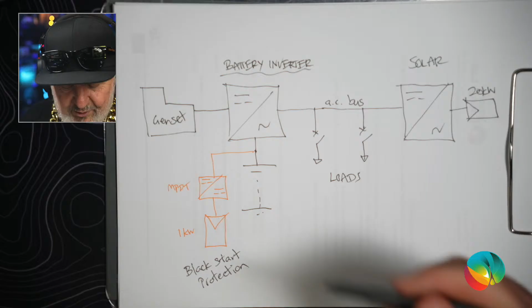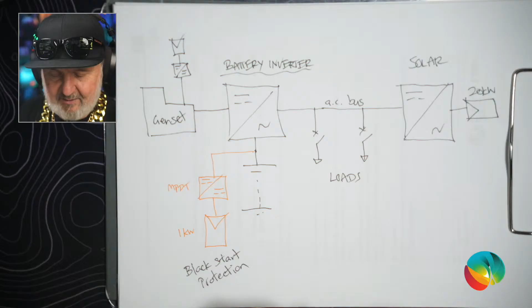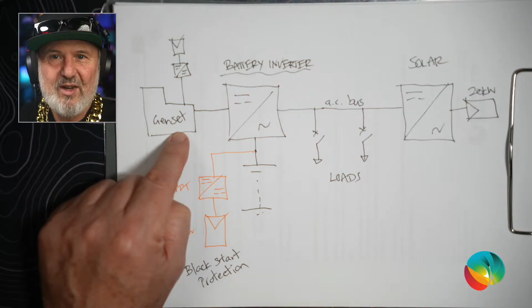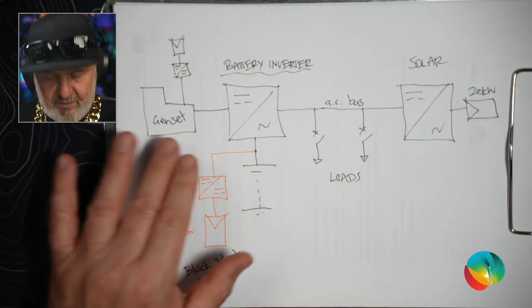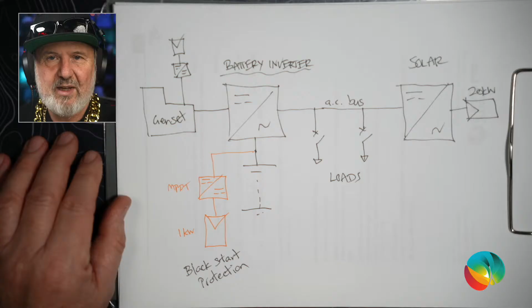Can I also suggest that if you're going to have black start protection, you should also have some way of charging the battery on your generating set. So put in even just a little one panel to keep the generator set battery charged up, because if you've designed this system to have a high solar fraction, that means you hardly ever use the generator. So here at the Smart Energy Lab, we don't run the generator for 6, 7, 8, 9 months of the year. So it's sitting there, and the battery would definitely die if I didn't have a trickle charge on it. And there's a simple trickle charge to keep the generator battery alive.